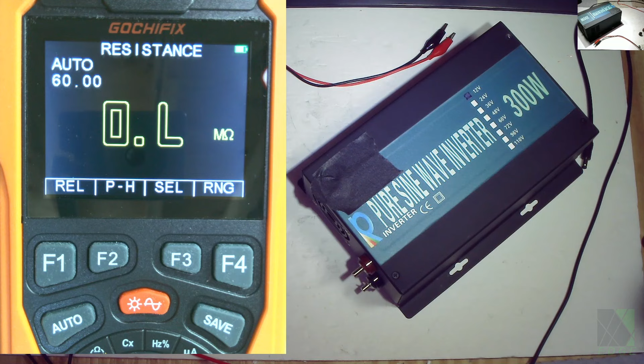If you see that on an inverter, first of all, do not try to reconnect it to your solar power system. Don't reconnect it to your battery banks, or reset the circuit breaker, or replace the fuses, because a short circuit means that the inverter requires repair. There's no way around it. It's going to require service. Probably a transistor or something on the input is shorted out, and it's all gone wrong, and it's going to need to be replaced.